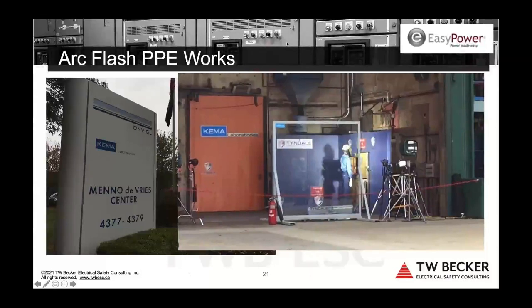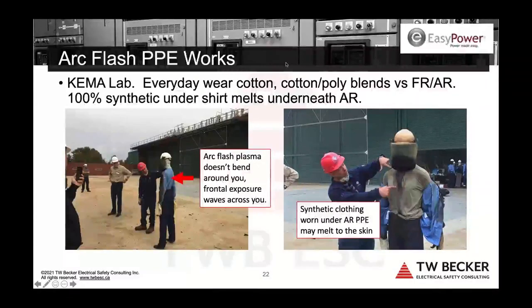So that's pretty horrendous. When you see an arc flash in person, it's quite the event. But that would have been probably less than 10 calories per centimeter squared. Now what you see in front of you is the actual mannequin. That plasma cloud's a wave. It doesn't bend. So you can see the back of the shirt is new. The front took the arc flash. And you see that blackening, that carbonization.